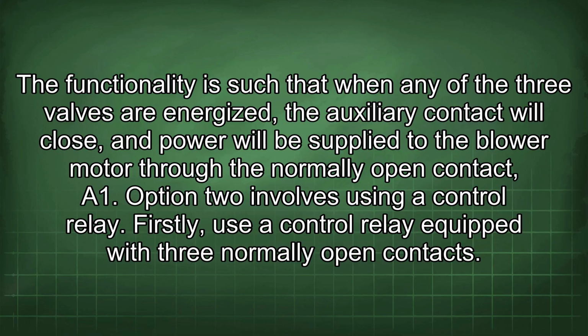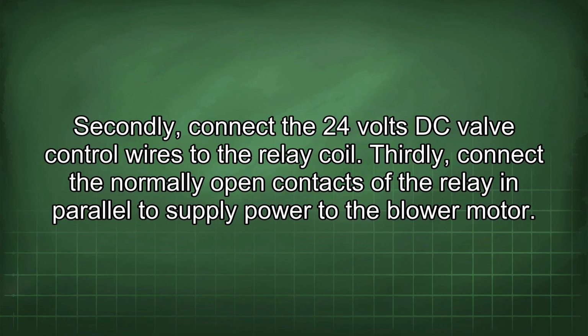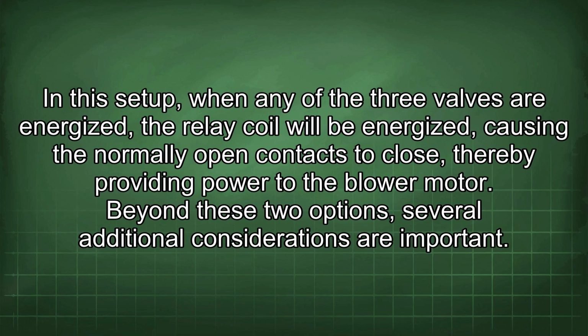Option 2 involves using a control relay. Firstly, use a control relay equipped with three normally open contacts. Secondly, connect the 24 volts DC valve control wires to the relay coil. Thirdly, connect the normally open contacts of the relay in parallel to supply power to the blower motor. In this setup, when any of the three valves are energized, the relay coil will be energized, causing the normally open contacts to close, thereby providing power to the blower motor.